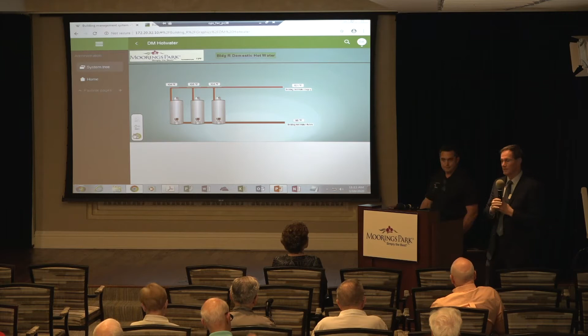Float switch is another example. So in every unit that I'm aware of, HVAC generates water off your condenser coils and collects in the condensate pan and is supposed to go to daylight through the condensate drain. Well, those condensate drains can become clogged. So if that starts to back up, it will trip a float switch and shut your unit off before it floods the floors, ideally. That's in place now? In most units, most everyone I'm familiar with, it will.